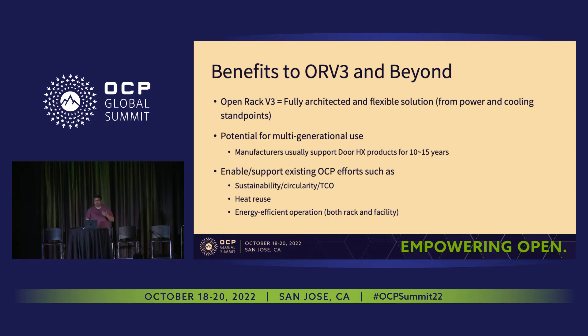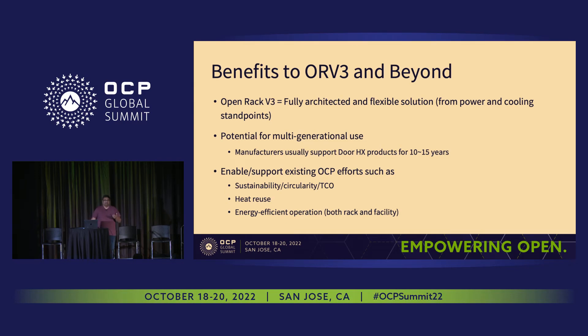Most importantly, we want to enable and support existing OCP efforts such as sustainability and the circular economy. Going back to the 10-year lifespan — is multi-generational use possible across the rest of the liquid cooling architecture in Open Rack V3? We're discussing this with the Cold Plate and sustainability groups at an early stage. A hybrid solution — cold plates plus a door heat exchanger — can support really high rack powers, and multi-generational use would be very appealing to companies deploying at scale that need to monitor their carbon footprint. Other facility-level initiatives like heat reuse and general energy-efficient operation also apply, and PUE will continue to be a relevant metric.